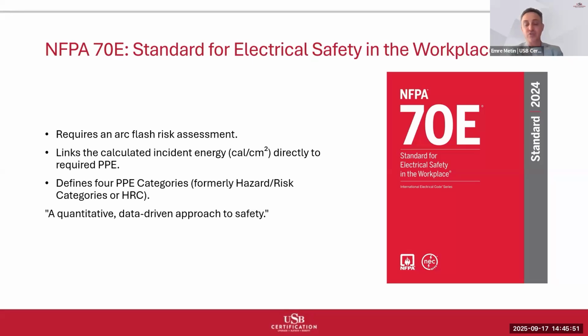The standard also includes tables for estimating PPE requirements when detailed analysis isn't available. But these tables are conservative estimates. Site-specific analysis usually provides more accurate and often less restrictive requirements. NFPA 70E represents a data-driven approach to electrical safety. Rather than relying on generic precautions, it provides specific, measurable requirements based on actual hazard levels at specific locations.